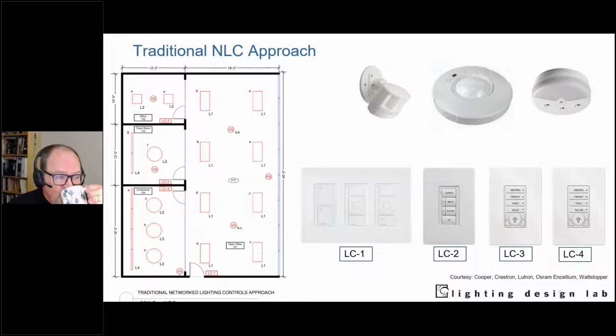A traditional networked lighting control system essentially has load controllers, so that they're aggregated together and we don't have all the sensors at each light fixture. In this particular case, I have split out control zones as such—control zone A and A, B, C, and D. The reason for that is twofold: one, I have a window wall here, so I need a primary daylight zone and then a secondary daylight zone. But I also want to split that up a bit more so I can have finer control, so I split it up along this axis. So these two are in the primary daylight zone.